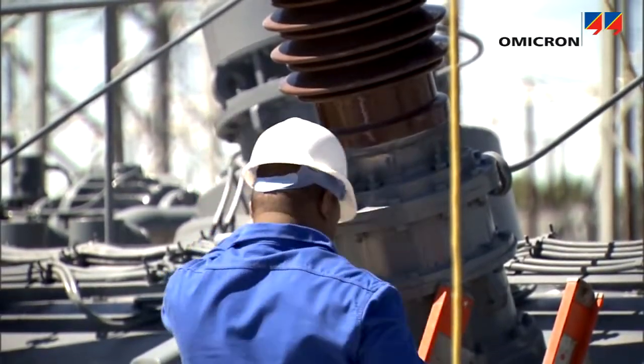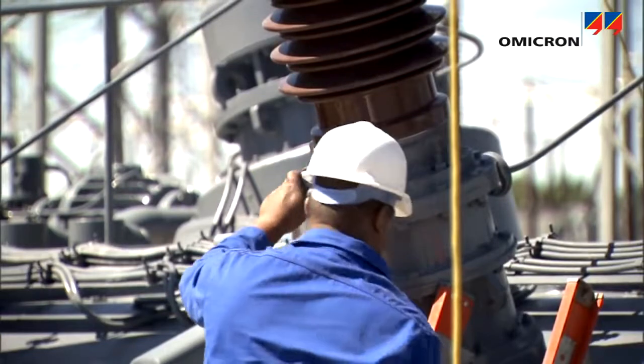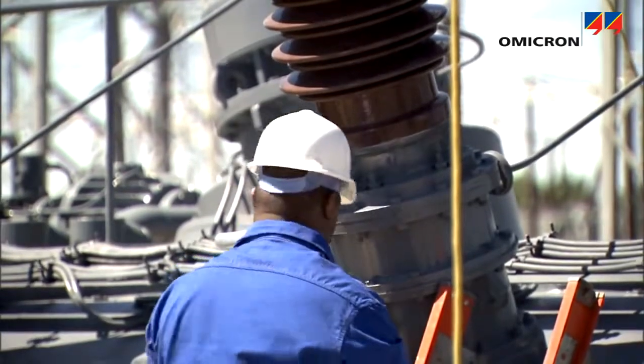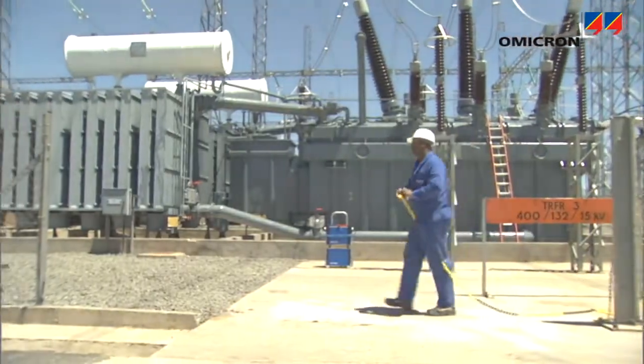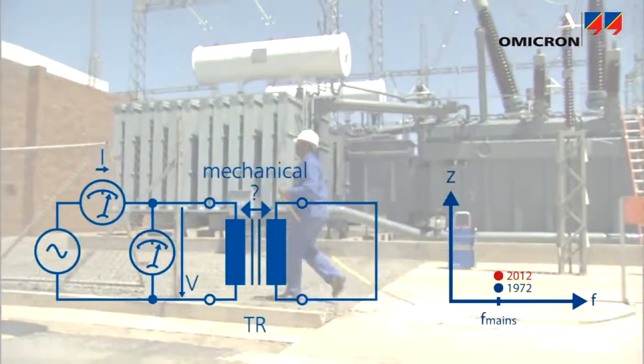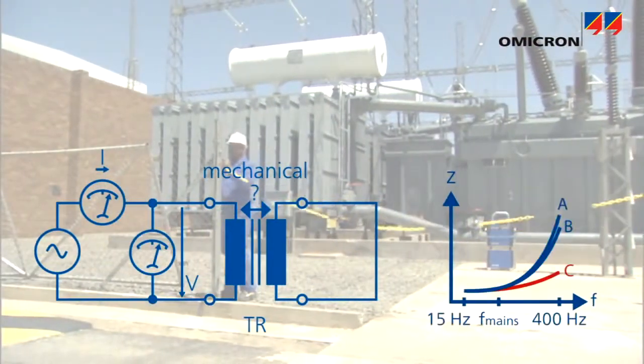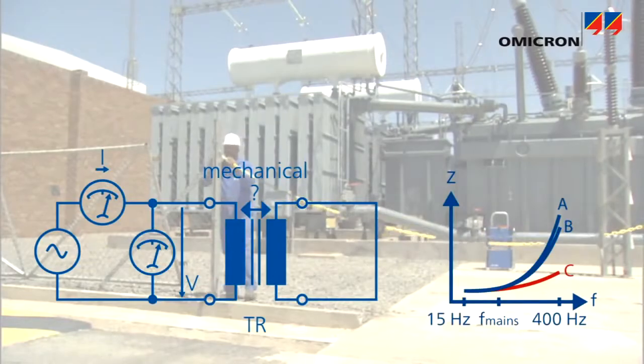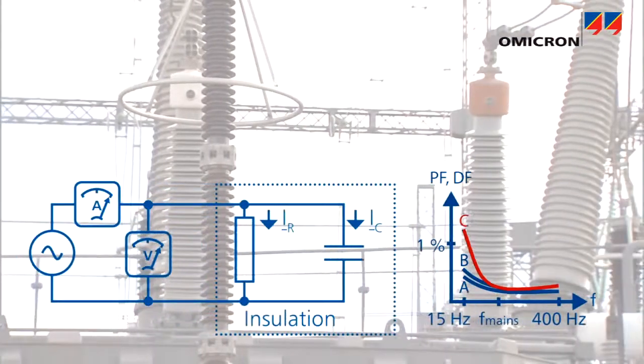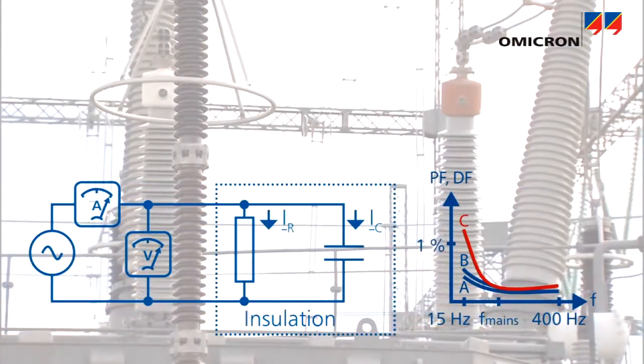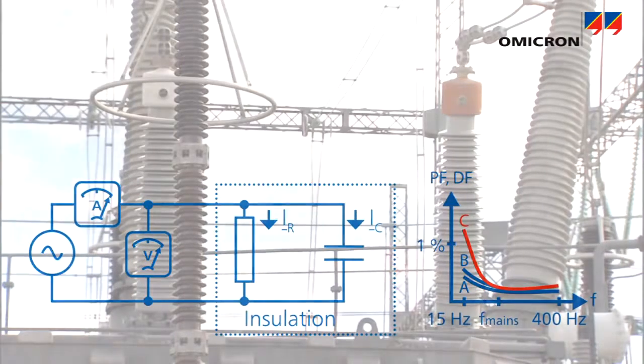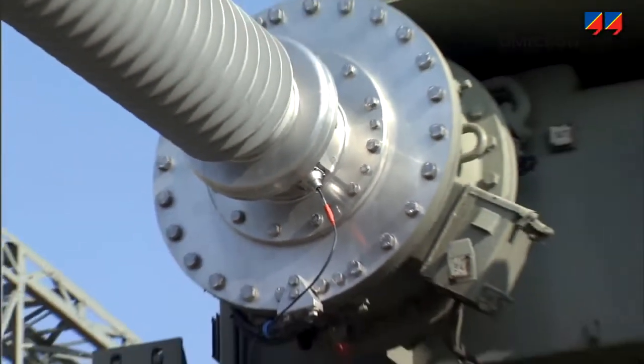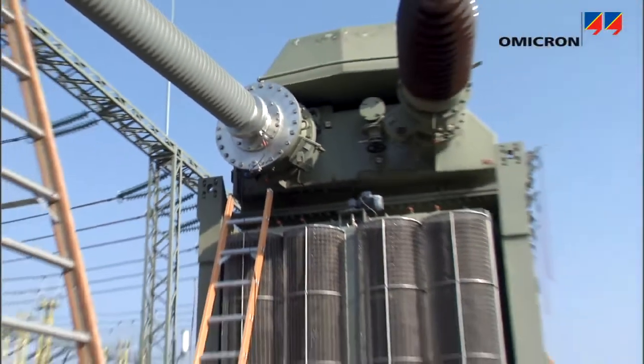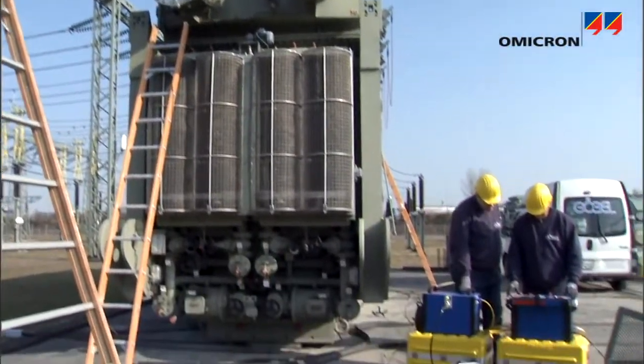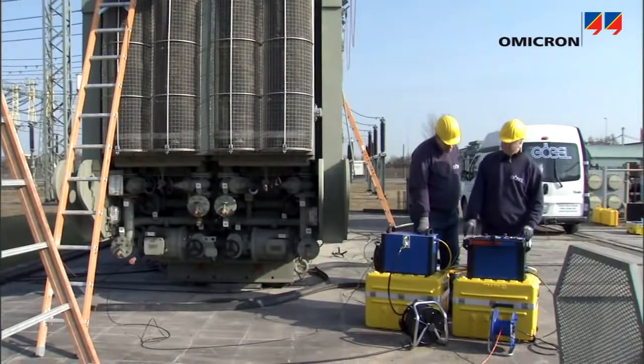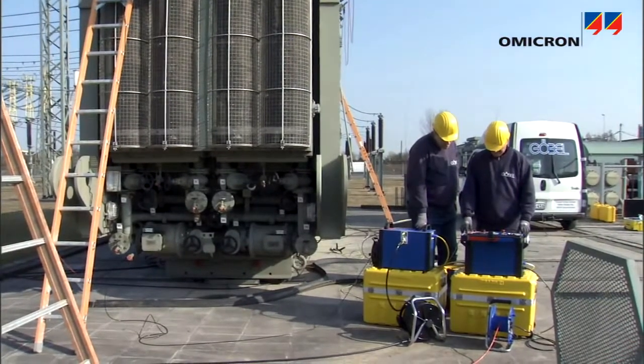After an electrical failure, winding geometry and insulation integrity may also be verified using advanced diagnostic measurements such as short circuit impedance or leakage reactance and frequency response of stray losses, or measuring power factor or dissipation factor over a range of frequencies. Through periodic and diagnostic measurement and maintenance efforts, utilities and service providers help satisfy the ever-growing need for a reliable electrical supply 24/7.